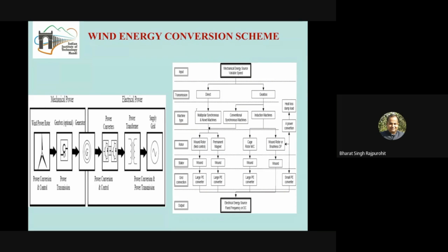So what is the basic scheme? The basic scheme has a wind turbine, generally a 3-blade system. Then a gearbox, which is optional in some systems. Why is the gearbox required? The gearbox is required to meet the speed requirement of an electrical generator. Electrical generators are designed for a higher rotational speed to keep their weight optimal, as per the flux requirement, and generally it is like 1500 rpm, 1800 rpm and so on. But the wind turbine, the 3-blade or 2-blade mechanism, rotates at a speed of around 15 rpm, or 12 to 18 rpm. So these are slow moving schemes.